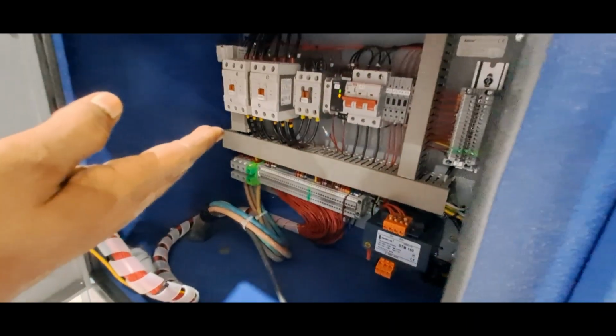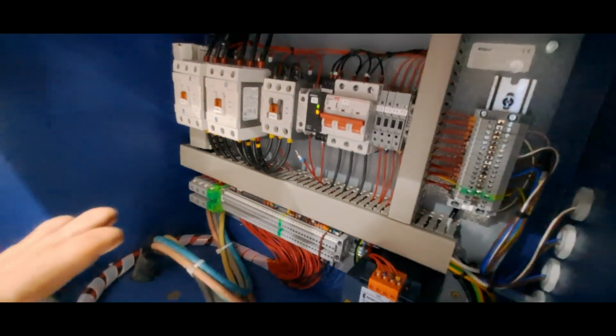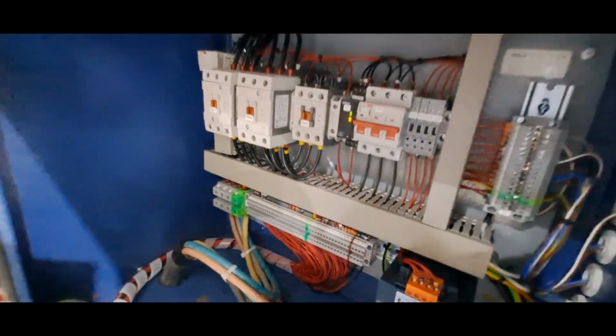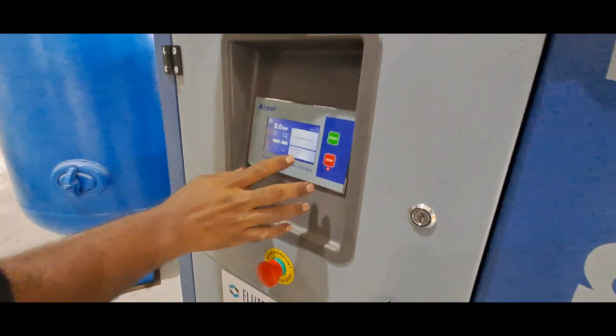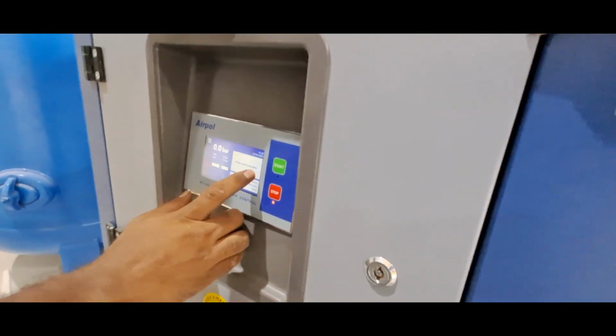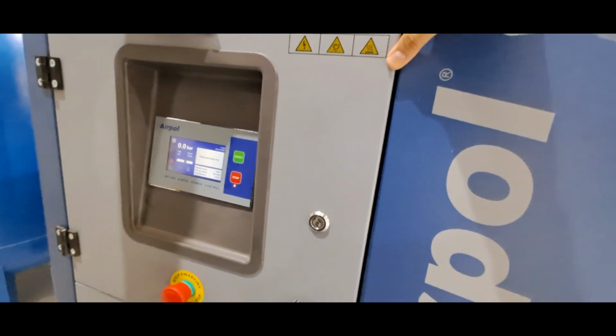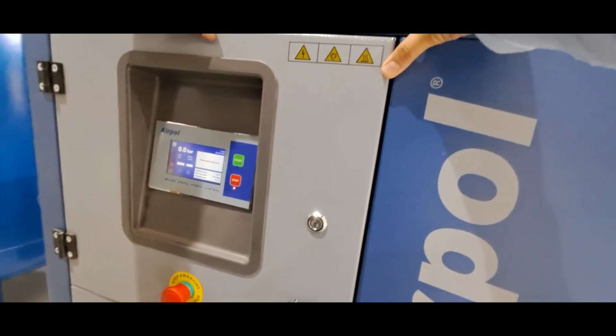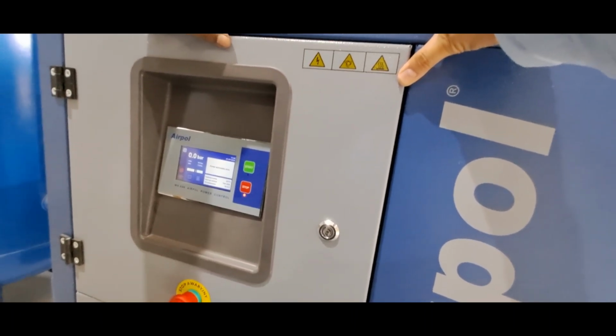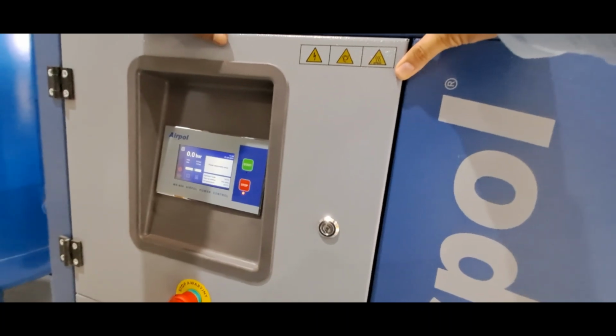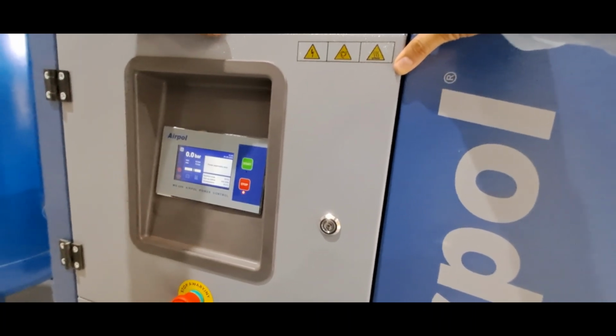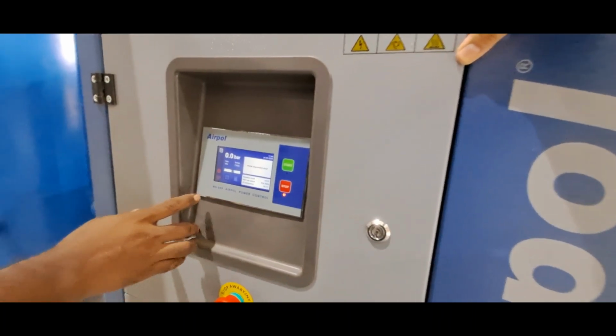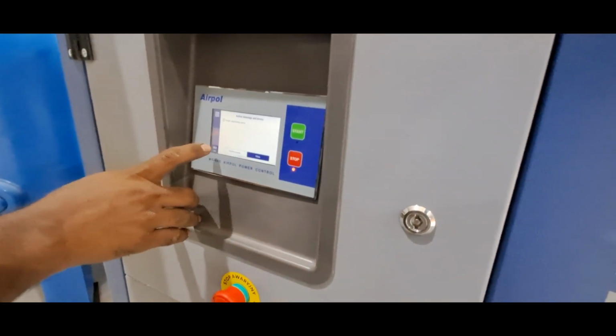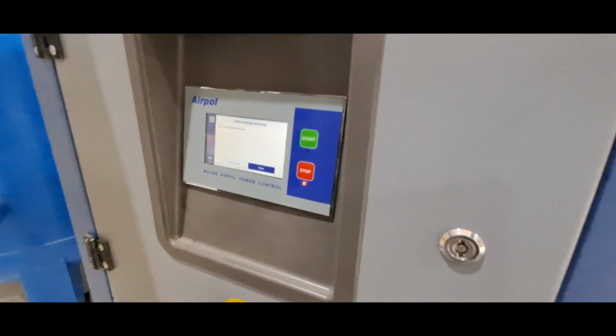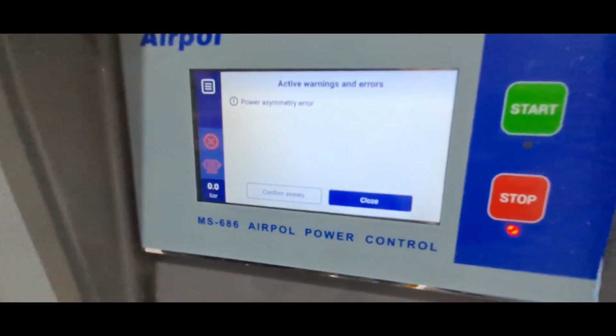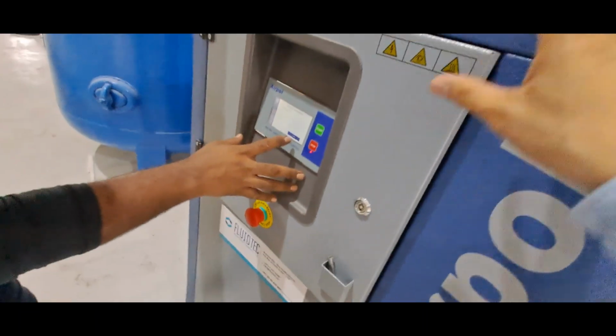We have disconnected the phase failure NC connection from there. Yeah, this one. So now the display is showing a power asymmetric error. Basically we mimic, or apply, the principle of if one phase is gone. That means you have R, Y, B. In case R is gone or disconnected, you have a single phasing issue. So the system detects that there is a power asymmetric error. Yes. Okay. Explain, Engineer Muhammad.